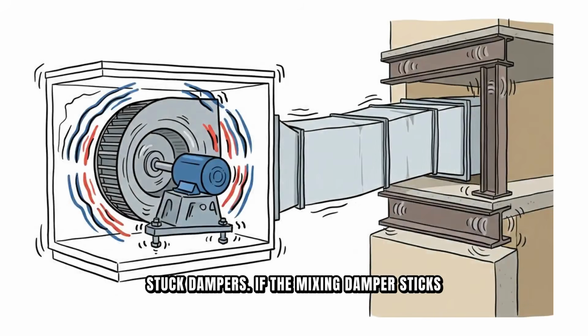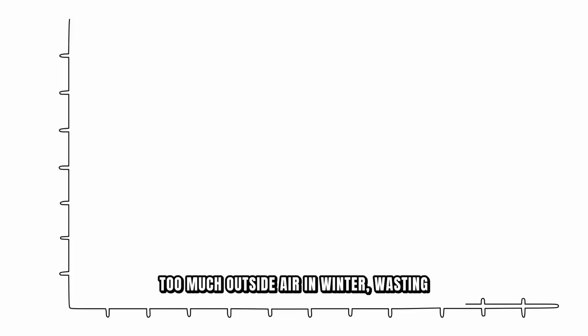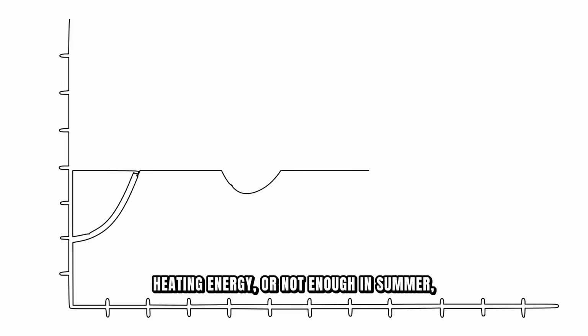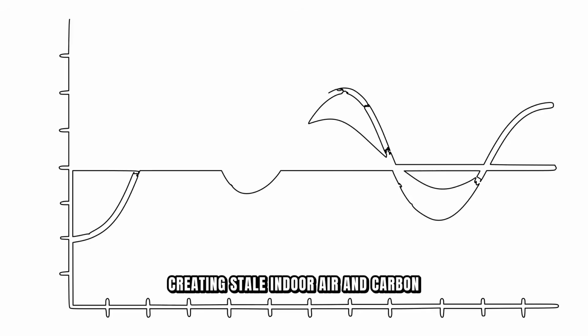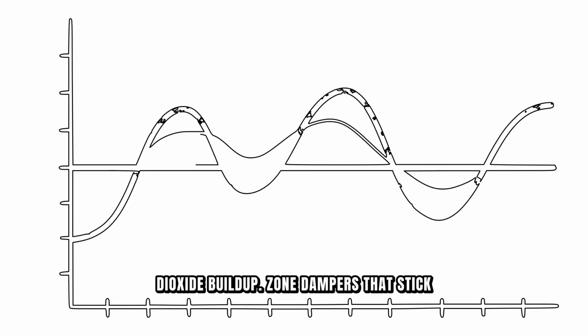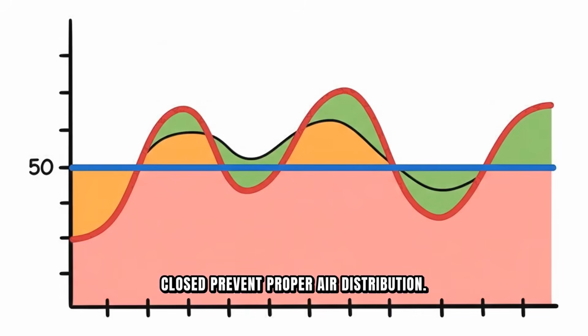Fifth is leaky or stuck dampers. If the mixing damper sticks in one position, you either bring in too much outside air in winter, wasting heating energy, or not enough in summer, creating stale indoor air and carbon dioxide buildup. Zone dampers that stick closed prevent proper air distribution. These should be exercised regularly and checked during maintenance visits.